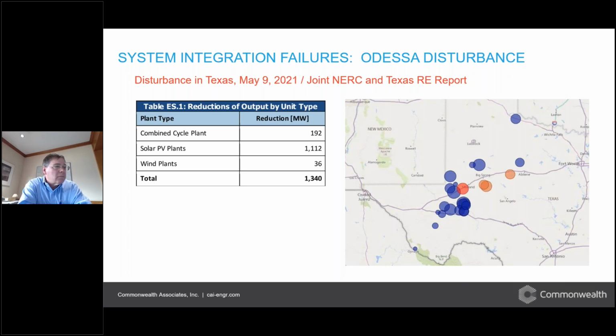Texas is a big state, and you can see how widespread that fault was, causing solar inverters to trip offline. All these faults were cleared in normal time, within a few cycles, but yet they caused the solar facilities to drop off.